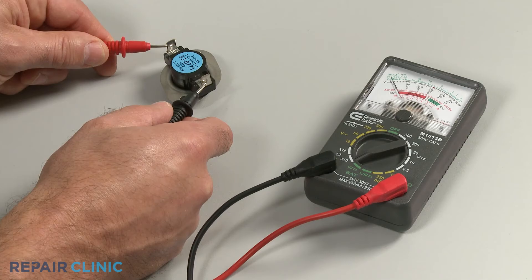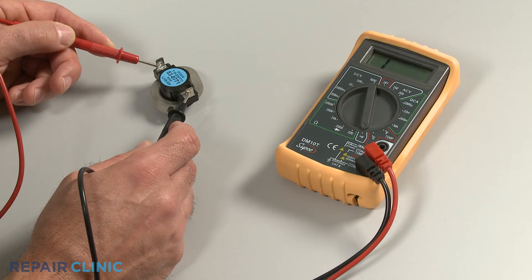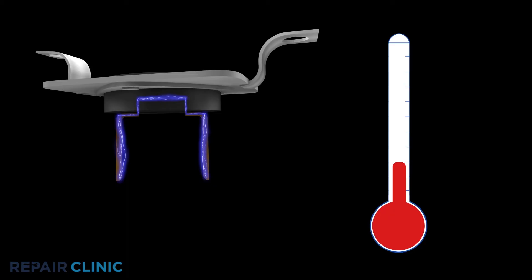If the meter's needle does not move, or the digital display does not change significantly, there is no continuity, which means the thermostat has failed and will need to be replaced.